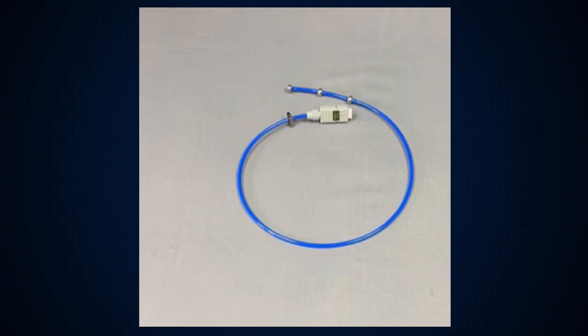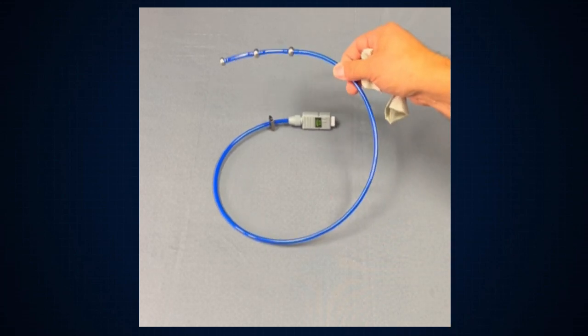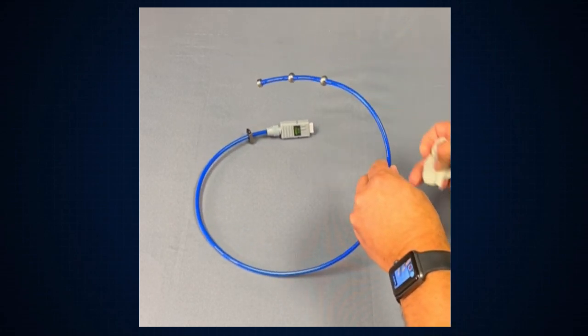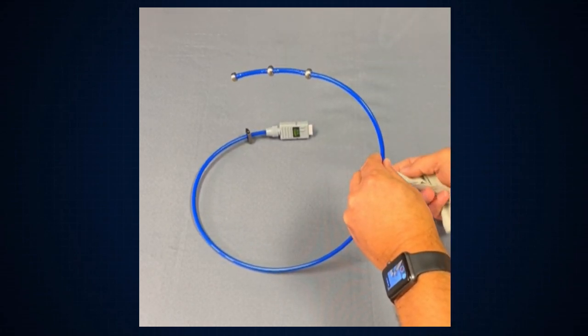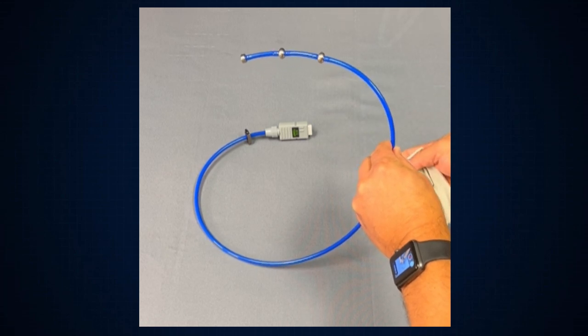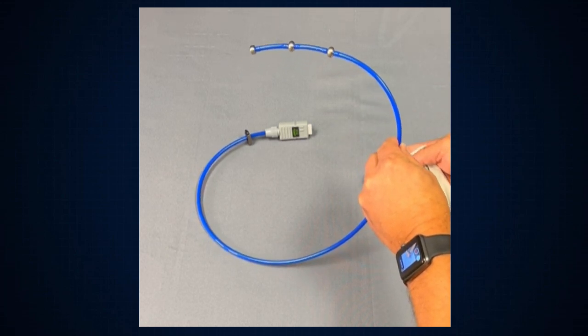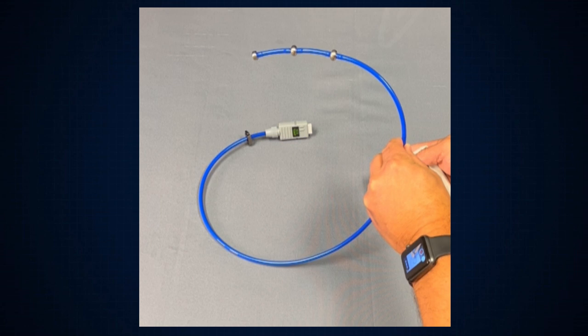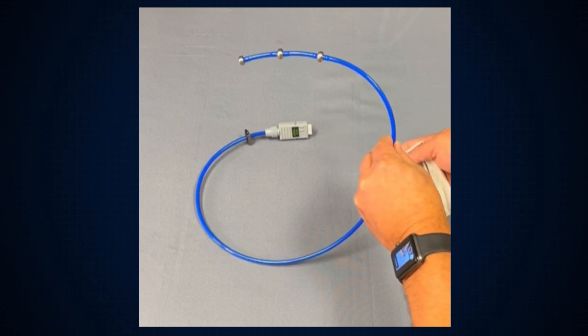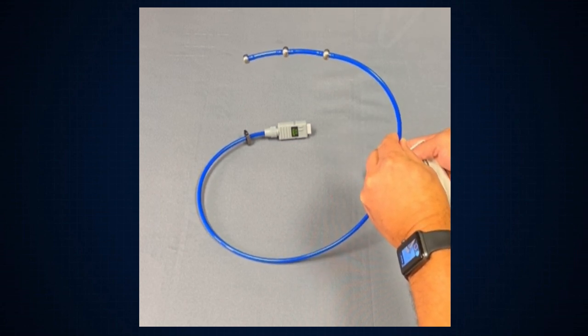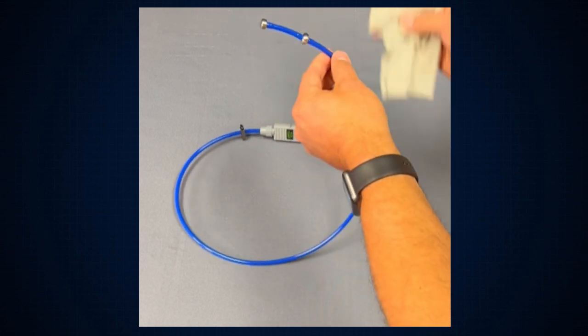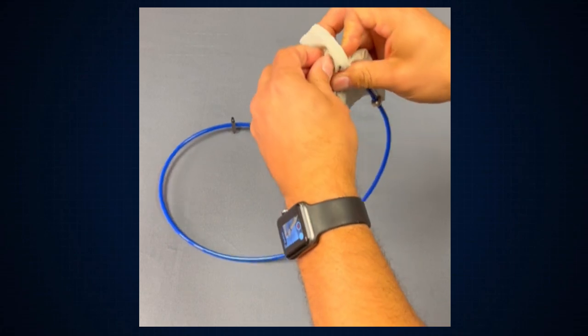While we're here, I wanted to go ahead and touch base on cleaning the esophageal ECG temperature probe. So at the end of any given procedure, just simply remove the probe from the esophagus. Go ahead and take yourself a 2x2 or a 4x4 with some dilute chlorhexidine, Nolvasan, or trifectant. Any of those cleaning agents will be just fine. A lot of practices will even have a canister prepared and ready with that gauze for cleaning. Take your gauze, just grab the probe, wipe the probe off, and that will keep the probe in nice good shape.